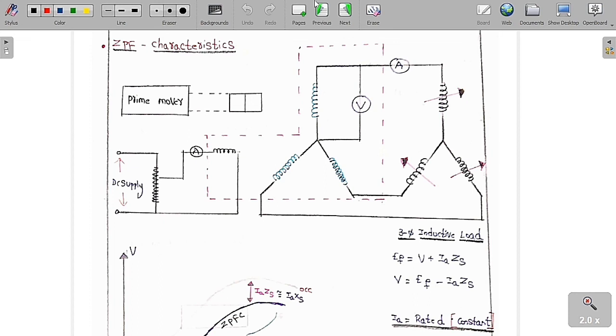Now we will see how to draw this and set up the test. As I already told you, we keep the field winding on the prime mover, and we always rotate it at a constant speed, which is the rated speed. This is the DC supply, and we give a variable DC supply because we need to change the field current.